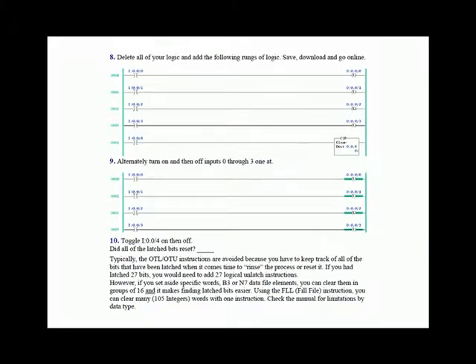The last thing we had you do in this section was the CLEAR instruction, which should be very clear to you — it just clears the destination. To show a possible application, we had you put in a bunch of latched output instructions and alternately turn on inputs 0 through 3 one at a time, which latches up the bits. Remember from an earlier lab that latch and unlatch do not have a false execution. So the latch instruction sets the bit, but when the rung goes false, the latch instruction has no false execution and doesn't do anything — if the last thing you did was set the bit to 1, it's still 1.